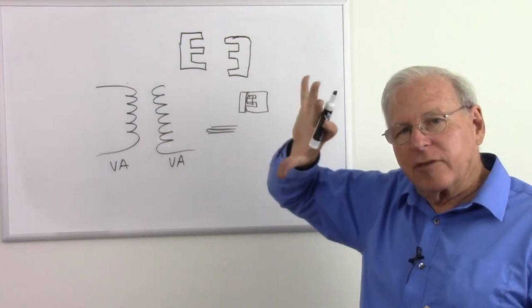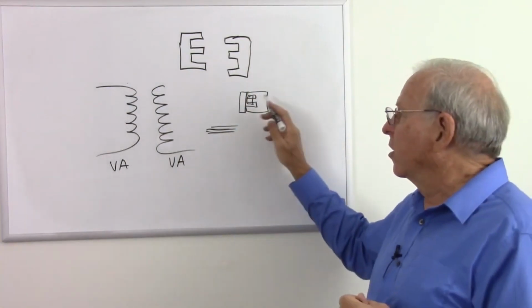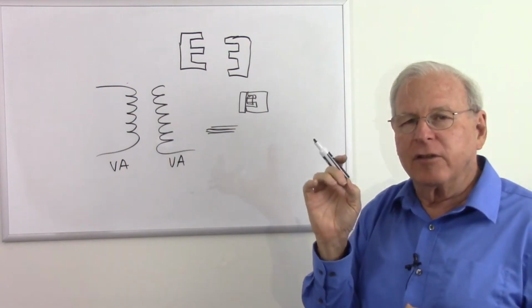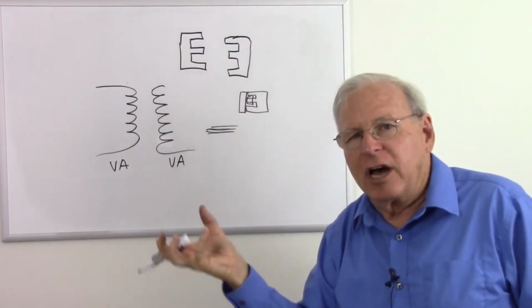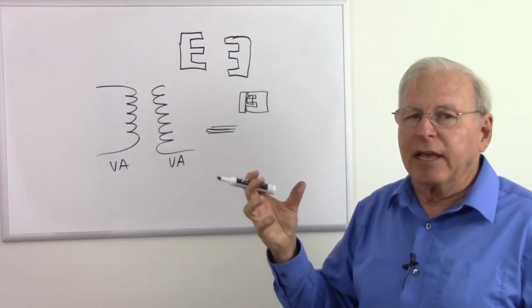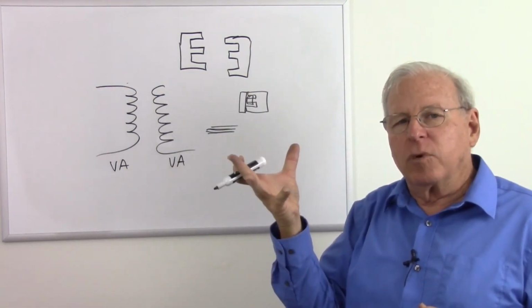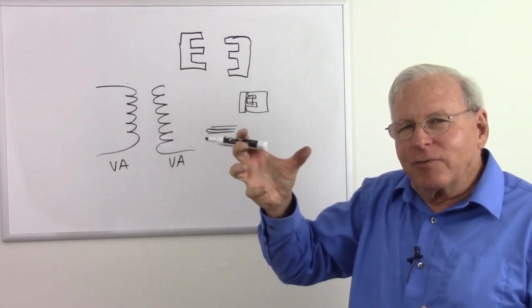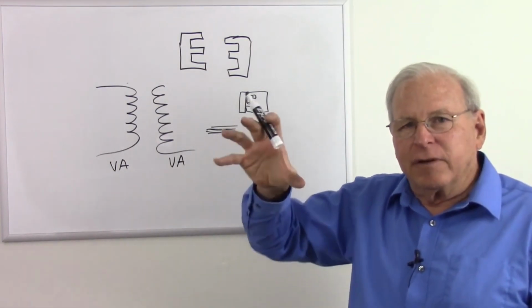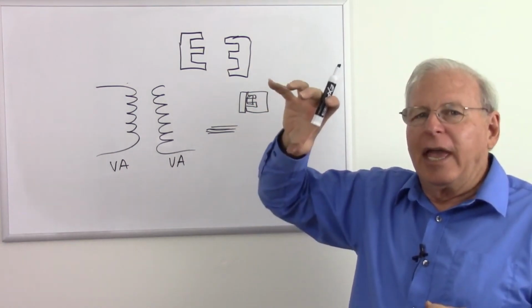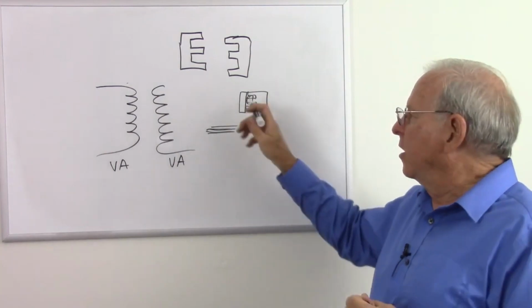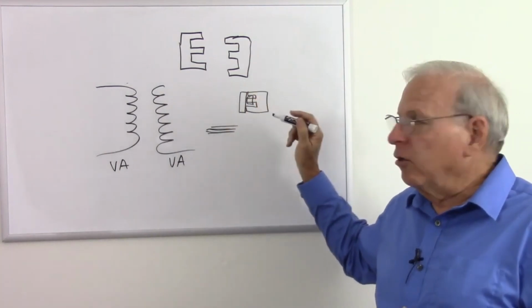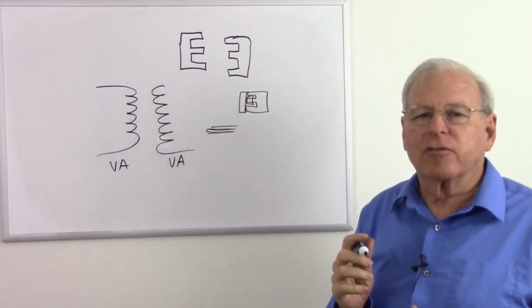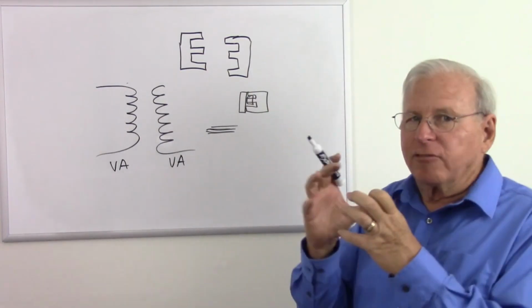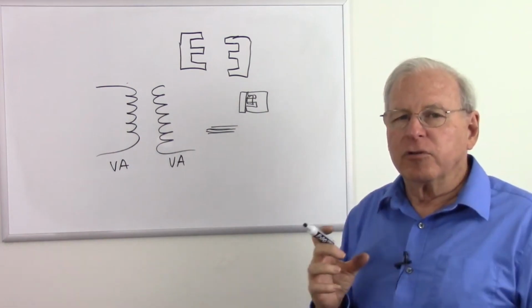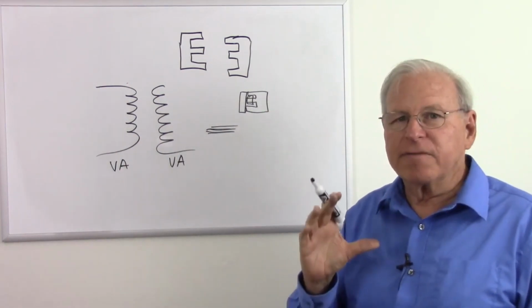This core gets magnetized one way, then magnetized another. We use silicon steel or soft iron because it doesn't hold the magnetism, but every time that flips, it takes a certain amount of energy to cause it to flip the other way, and that produces heat, and that's called hysteresis. So we flip the magnetic field one way, we try to flip it the other way, it resists, and then snaps. And that resisting of flipping the magnetic field is called hysteresis, and it does produce a little bit of heat, so we have a little bit of hysteresis. We use silicon steel because it doesn't hold magnetism, which reduces that hysteresis. And one more loss would be actually the physical vibrating of the core could produce heat. That's another type of loss we have, but they're very, very efficient.